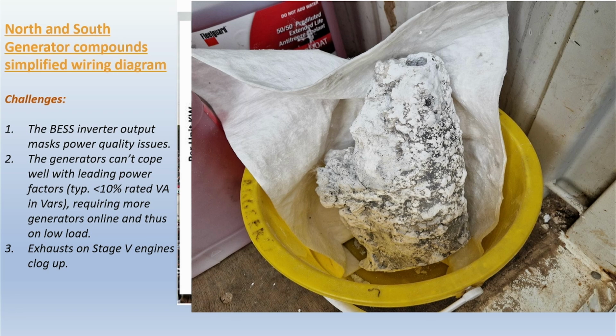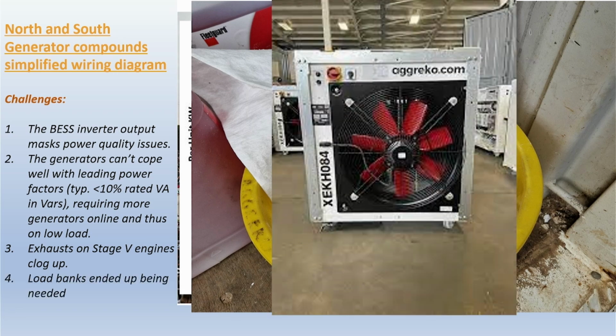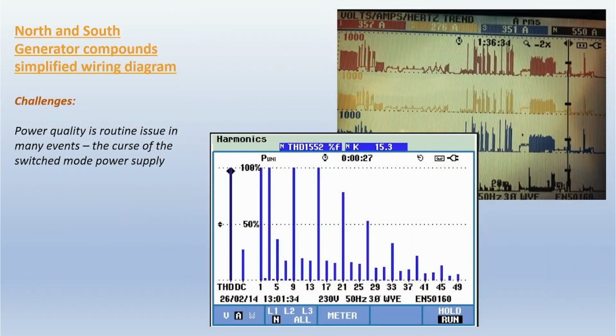A way to cure that is with load banks. So you stick big resistive loads onto the system to keep the generators happy because of the leading power factor issues. The other issue is harmonics as well, because switch mode power supplies really are the curse of any power system generally. You can see on the screen grab of a power quality analyzer, top right, a certain big festival that we all know and love.